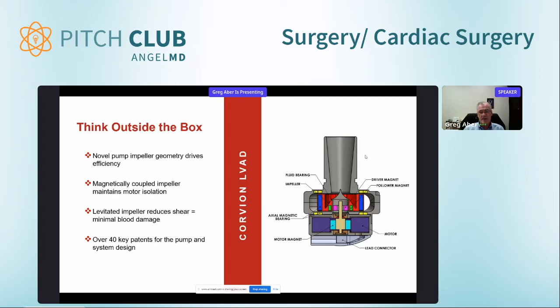You can see here hemolysis testing on the left. You know, as you lyse red blood cells, you release hemoglobin into plasma, and so the plasma becomes more red. So this is a direct comparison of our device to the Abbott device, where we pumped the same volume of blood from the same animal at the same time. And you can see our plasma stayed much more clear. And also in the analytical data, our free hemoglobin levels were about 70% lower.